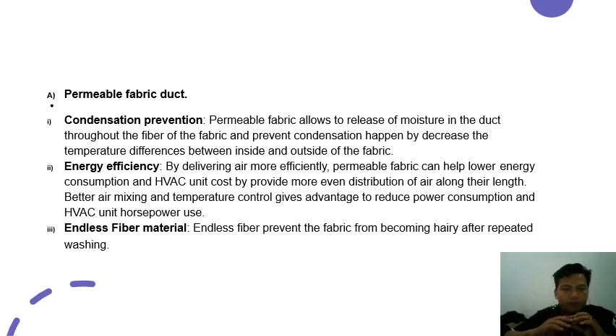The second one is permeable fabric duct. It is condensation prevention. Permeable fabric allows the moisture in the duct to be released through the fibers of the fabric and prevents condensation from happening by decreasing the temperature difference between inside and outside of the fabric. The second one is energy efficiency. By delivering air more efficiently, permeable fabric can help lower energy consumption of the HVAC unit by providing more even distribution of air along its length. Number three is endless fiber material. Endless fiber prevents the fabric from becoming hairy after repeated washing.